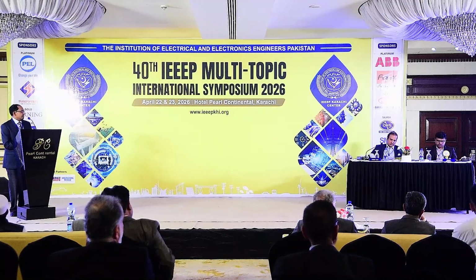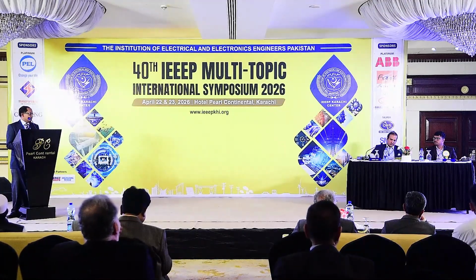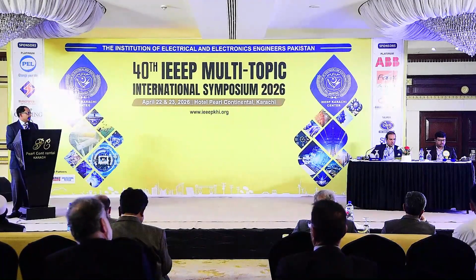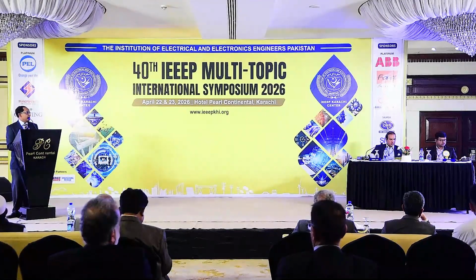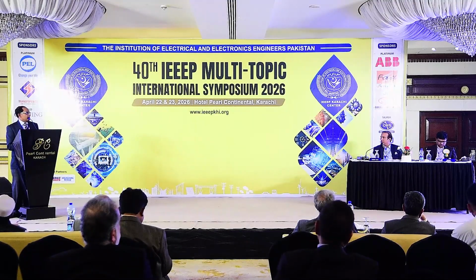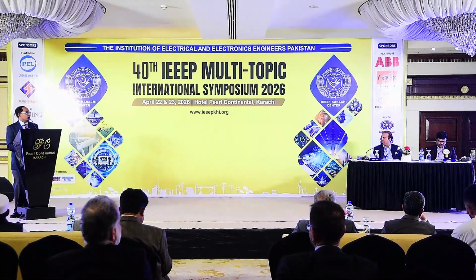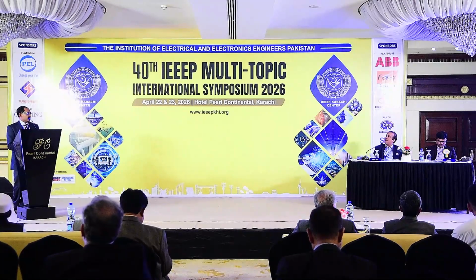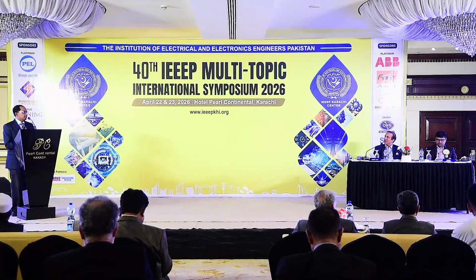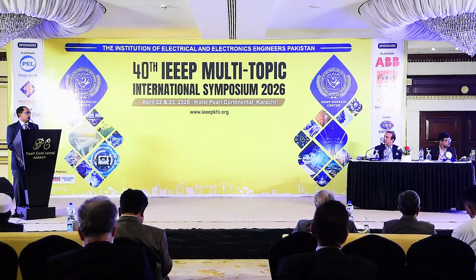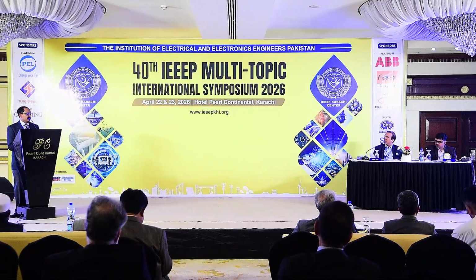In synthetic inertia control mode, there is a limitation: it is very fast and provides a certain backup for a few milliseconds. After that, the system moves on to normalizing the voltage stability of the system through droop control mode. Overall, this is achieved through a battery energy storage system, and the ratio between the inertial support and the droop control mode for a balanced system is usually 25 to 75 percent.